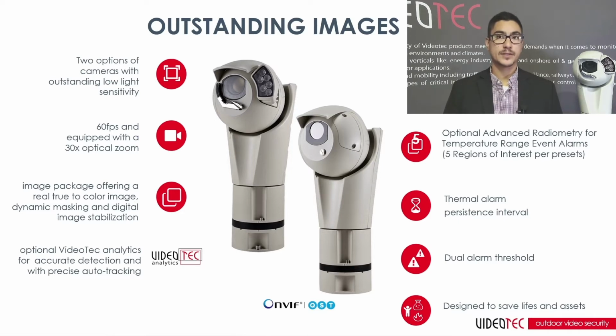The Evo standard thermal version can be offered with 336 by 256 or 640 by 512 resolutions and different lens options. The standard thermal is typically used for security applications like perimeters and surveillance. The advanced radiometry offers more precise, accurate temperature readings with an accuracy within plus or minus 5 degrees Celsius, and is typically offered for temperature monitoring and process control applications.